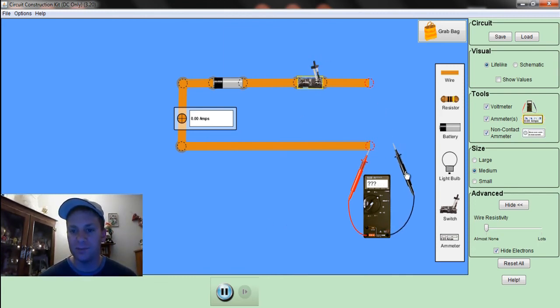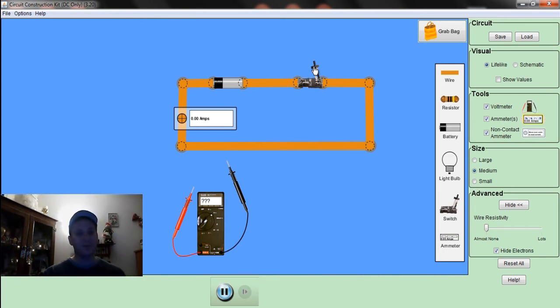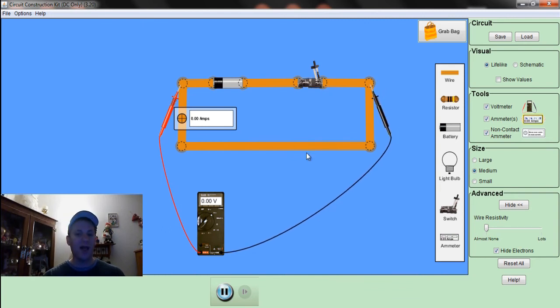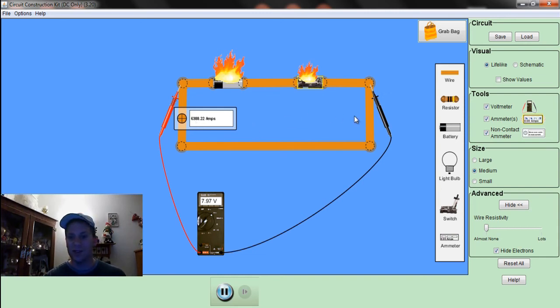Let me throw the switch, connect the meter, and throw the conductor back in. As I illustrated before, the simulator should act the same way — if I throw this switch something bad should happen, because this is a short circuit. These wires are all connected to each other. You shouldn't have voltage on a single wire; the voltage should drop on the load side. If voltage goes to ground it's a short circuit, and we have no fuses to protect this circuit. Look at the amps — there are over 6,000 amps, and I have voltage on this wire. My voltage didn't drop, so I'm putting voltage to ground. That's an example of a short.